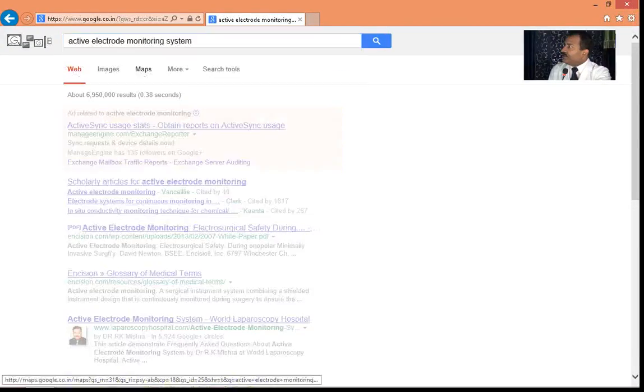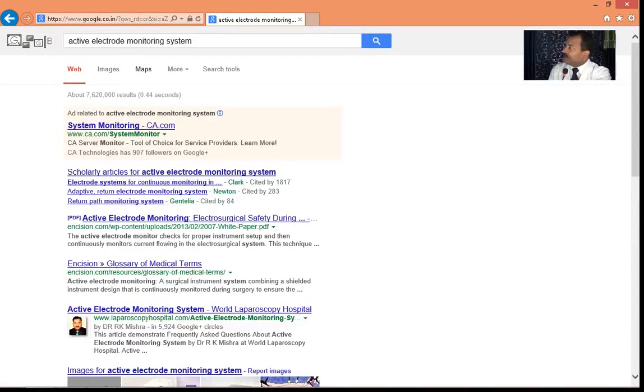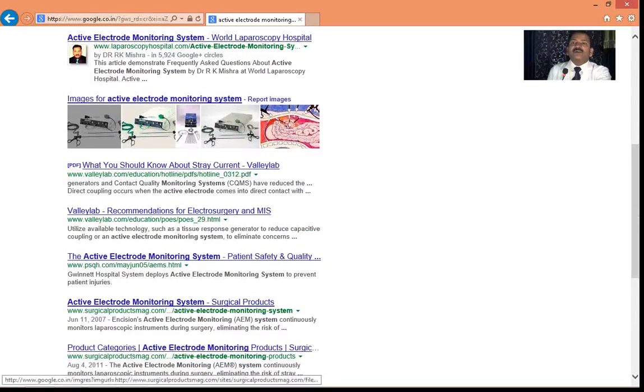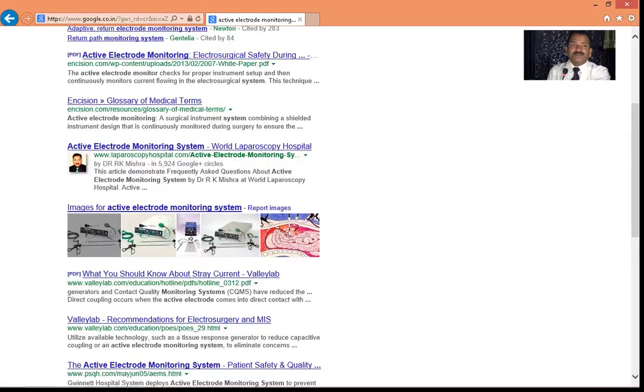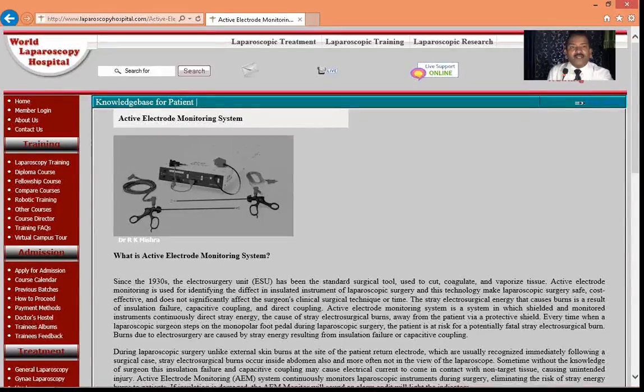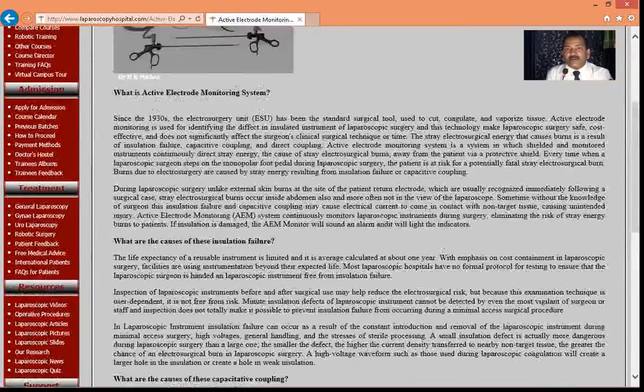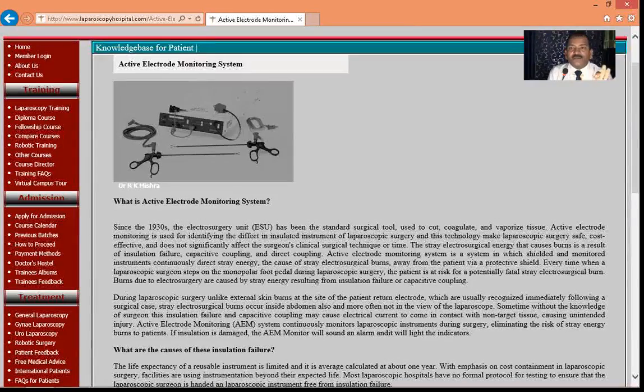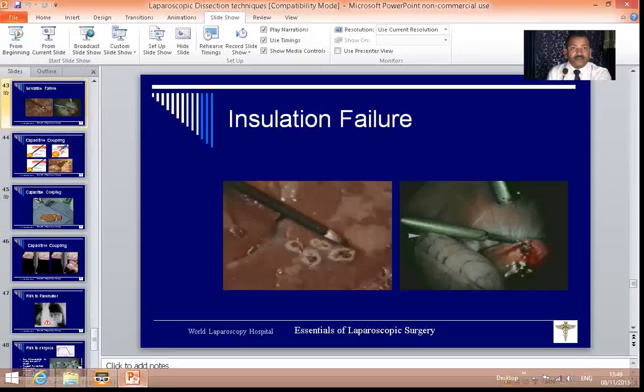There are a lot of companies making these equipments. The active electrode monitoring system has the advantage that if there is insulation failure, direct coupling, or capacitive coupling, it gives you an alarm: please remove instrument number 5 on cannula number 6, insulation has failed. Otherwise, you have to inspect it yourself carefully.